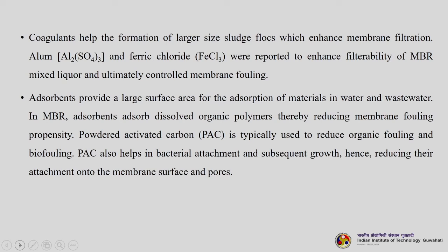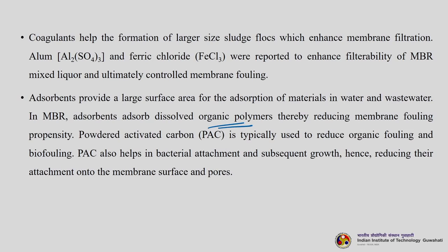And then you can add adsorbents also. They have a very large surface area for the adsorption of materials in water and wastewater. What they adsorb depends upon the charge based interaction of the component that is to be adsorbed on the surface of the adsorbents. So, they adsorb dissolved organic polymers, thereby reducing membrane fouling propensity. Powdered activated carbon can be used because its surface area is far higher than that of granular activated carbon, to reduce organic fouling and biofouling, but the problem with powdered activated carbon is to filter it, basically take it out.